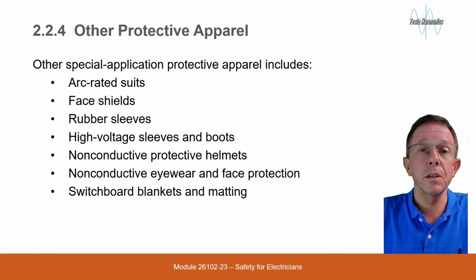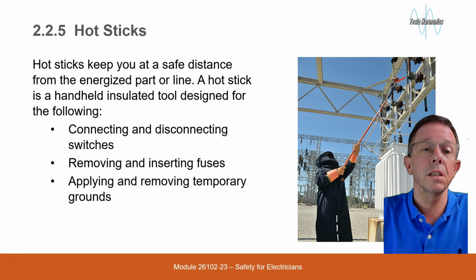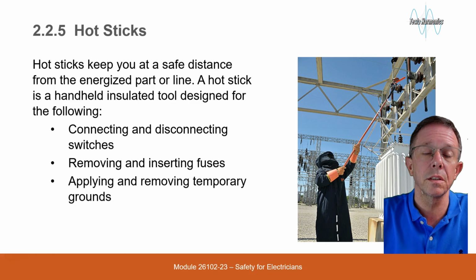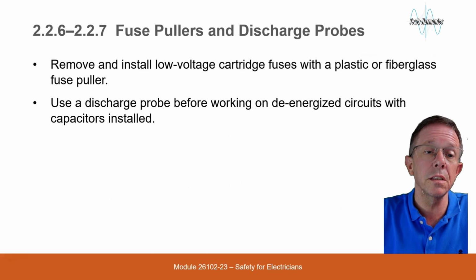Other protective apparel. Other specialized application protective apparel includes arc-rated suits, face shields, rubber sleeves, high-voltage sleeves and boots, non-conductive protective helmets, non-conductive eyewear and face protection, switchboard blankets, and matting. Hot sticks. Hot sticks keep you at a safe distance from the energized part or line. A hot stick is a handheld insulated tool designed for the following: connecting and disconnecting switches, removing and inserting fuses, applying and removing temporary grounds.